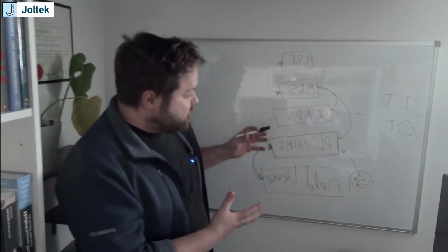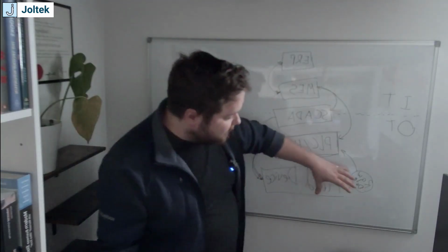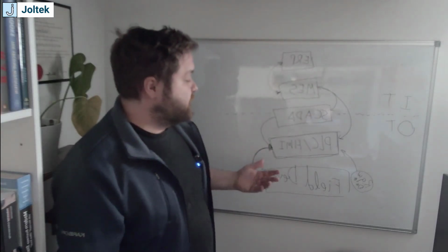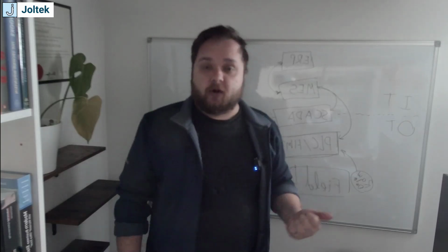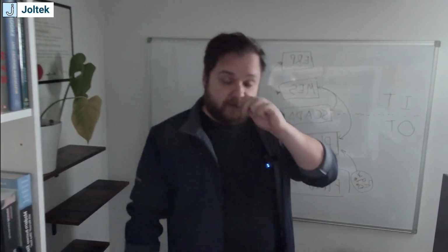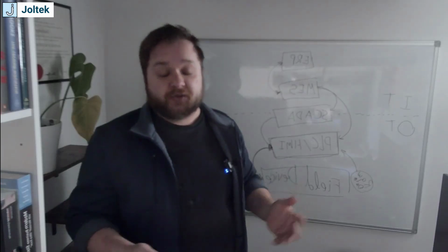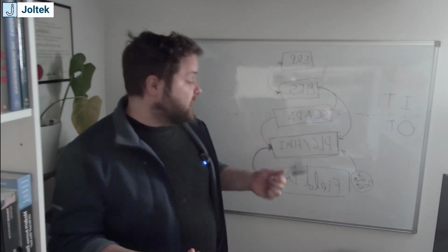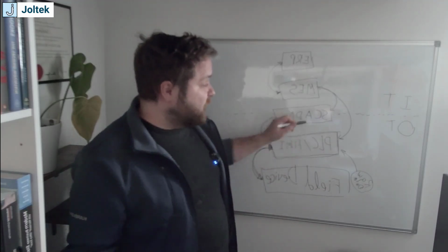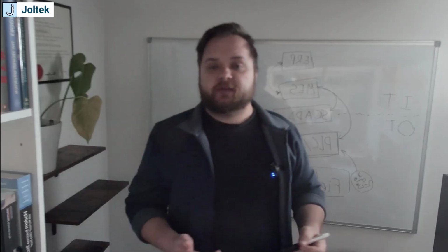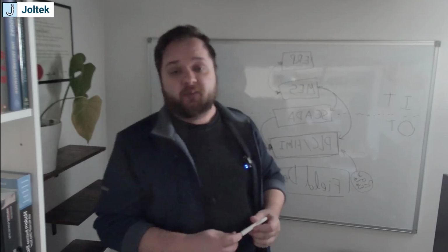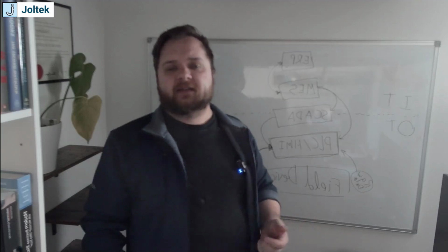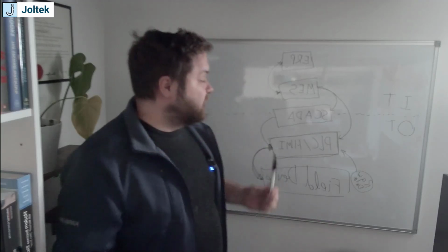So as you can visualize the stack, you can see how the raw data is going to slowly shrink as you move up the stack. And the reason for that is obvious, right? Because ultimately your PLCs need to understand all of the data. If you have a sensor that's not being utilized inside of your PLC, you might as well remove that sensor. If it's not going to some kind of a hub, if it's not making some kind of a decision, it is a useless device. Similarly, your SCADA is not going to ingest every single data point that's coming from the PLC, because you're looking to understand critical points, you're looking to understand fault codes. You don't need to have data that is cluttering, so to speak, at the SCADA level.